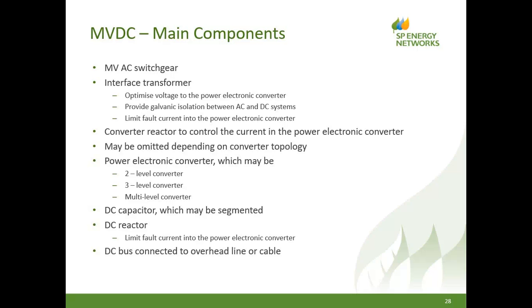So there is no path for DC current to flow from the DC side to the AC side, which is obviously good for the AC network. And it acts as an impedance to limit fault current into the power electronic converters. If there's a fault on the DC side of the converter, for whatever reason, fault current will be limited by the impedance of the transformer. So we don't destroy any equipment. We would trip under control and not cause any damage to equipment.